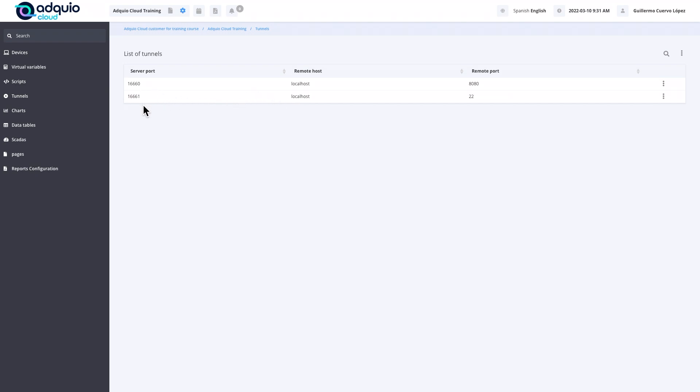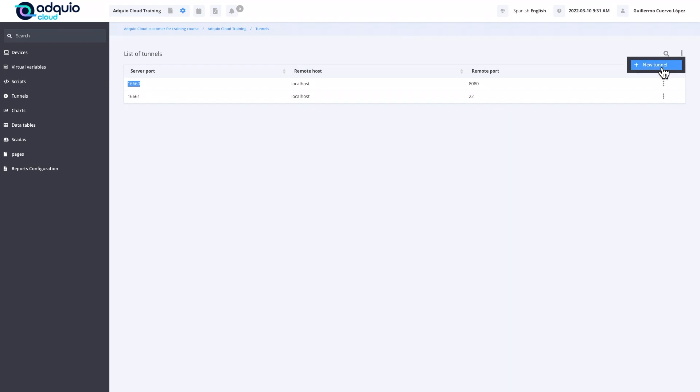The first thing we should know is that Adquio allows you to generate up to five different tunnels against devices of our facility. In this case, by default, it already has two tunnels created. Each of the tunnels will work on a different port, and these ports are based on the number of the Adquio device, which in this case would be 931666, removing 9 and 3 and adding a counter from 0 to 4. That is, the next number available would be the 16662.